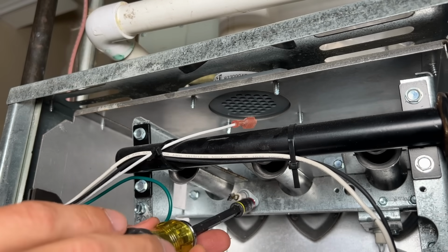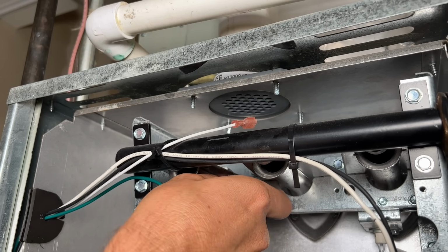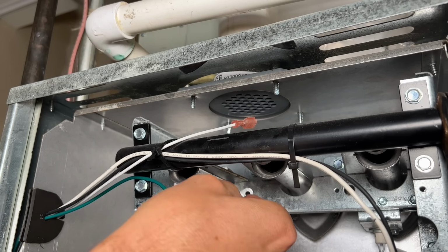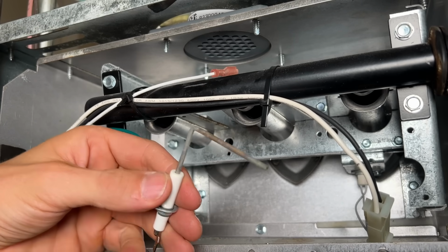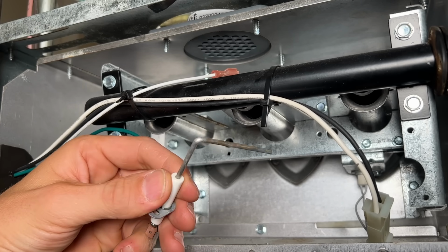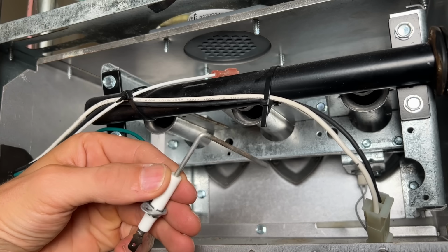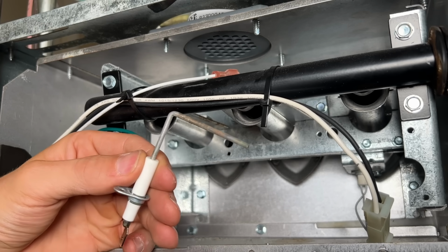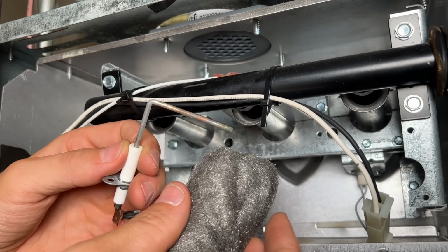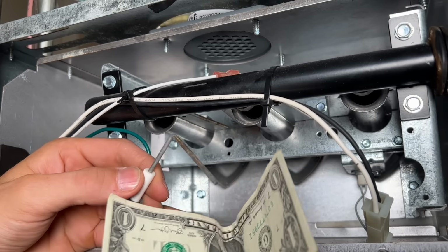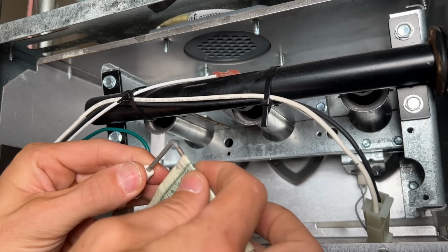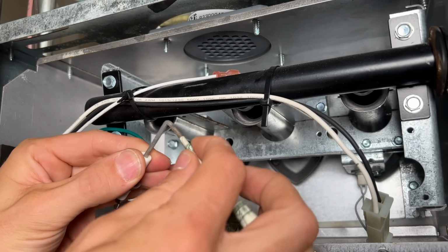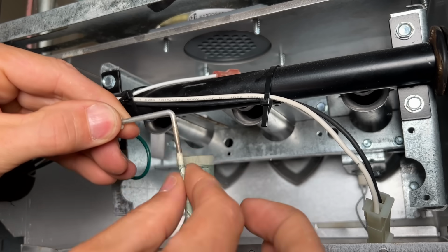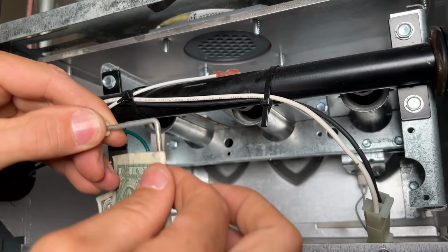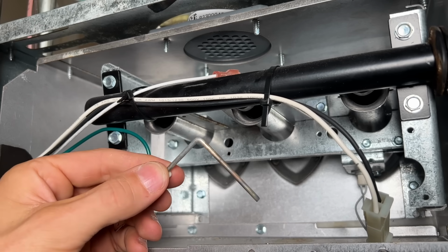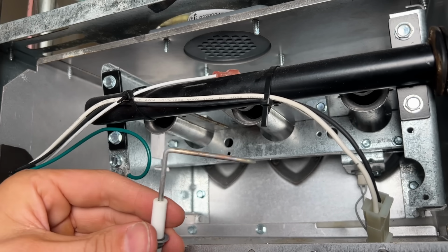And we got a magnet in the base there, which helps me pull the screw out. And then I'm able just to pull that flame detection sensor out. And then what we're looking for is any carbon buildup on that rod. If there is carbon buildup, that can impact its ability to sense that flame and be the source of your issue. So cleaning's super simple. You can either use something like steel wool if you have it around, or even just a $1 bill where you'll just work it across that rod, working off any of those carbon deposits. And then once the carbon deposits are removed, you should be good to reinstall and then test this out.